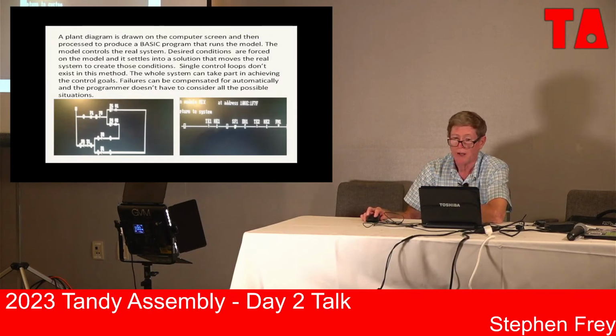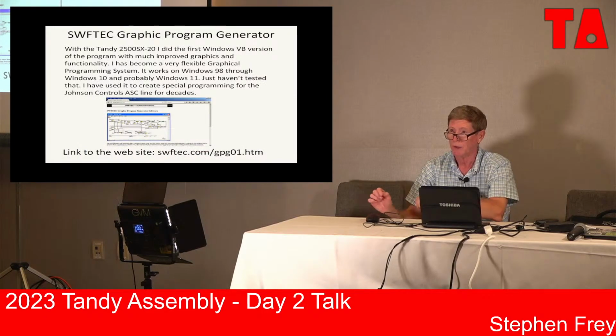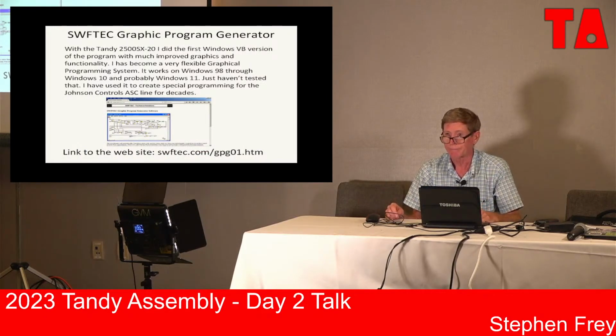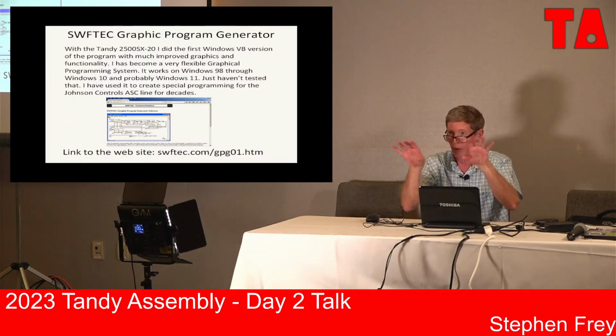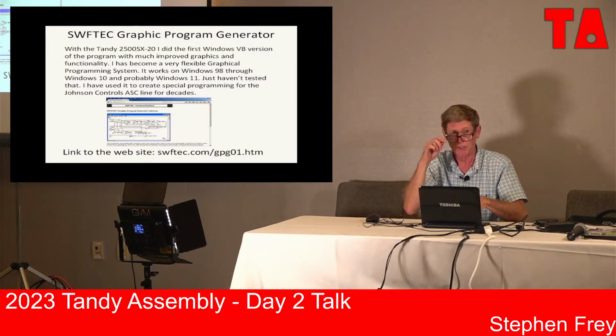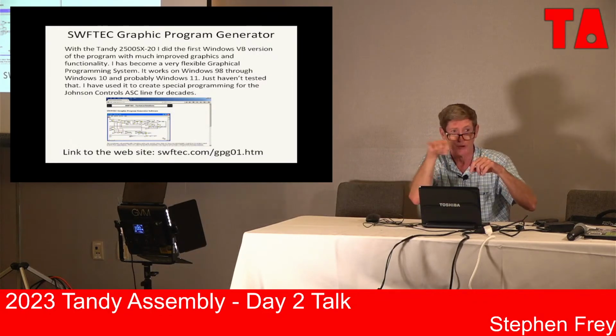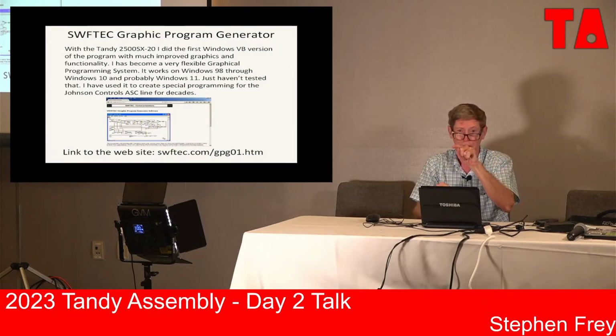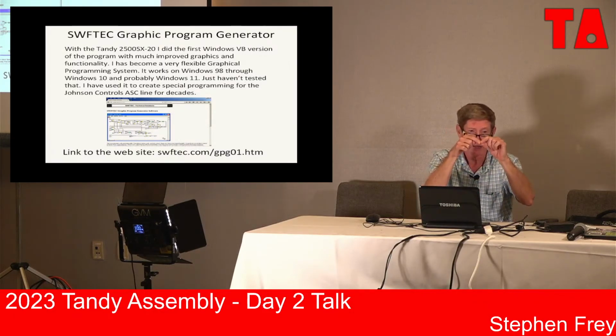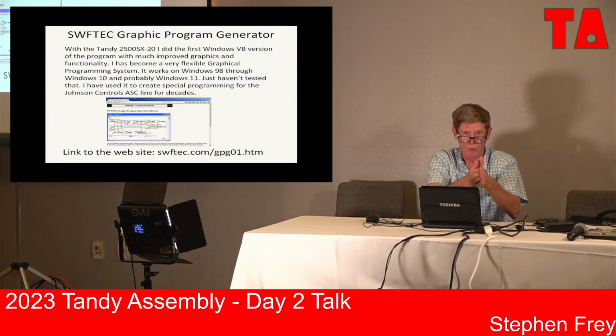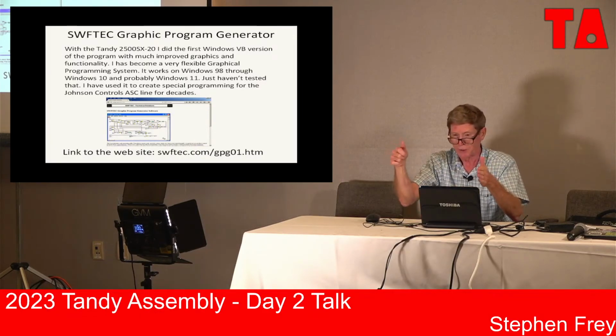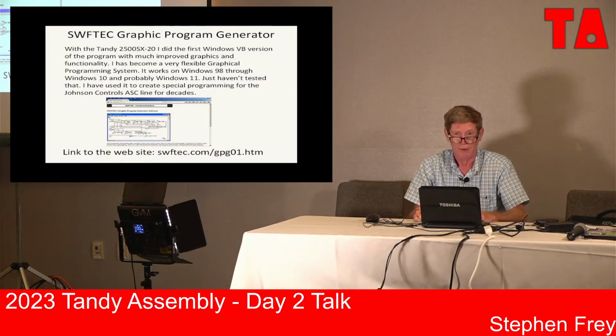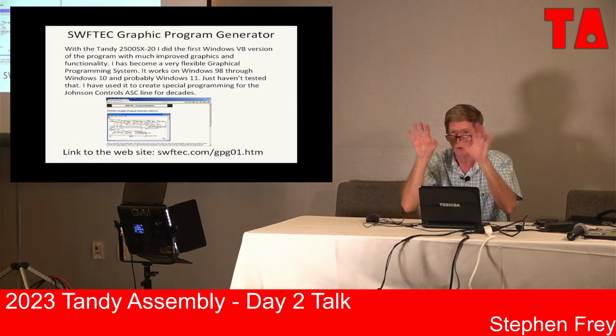The idea of model-based control is that you produce a model. Normally you think about control systems being like PID loops or control loops. This temperature sensor feeds back to a controller that works this valve, controlling the water flow through this hot water coil, and based on your setting, it works that valve to keep the temperature here what you want. That's your typical single loop type stuff.